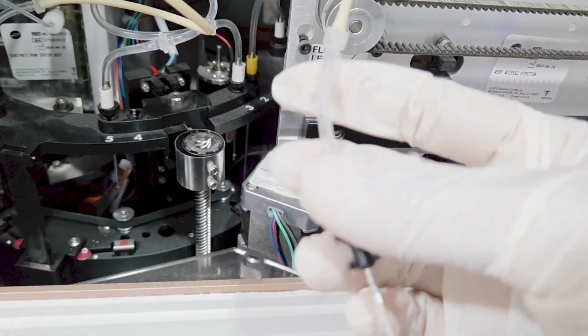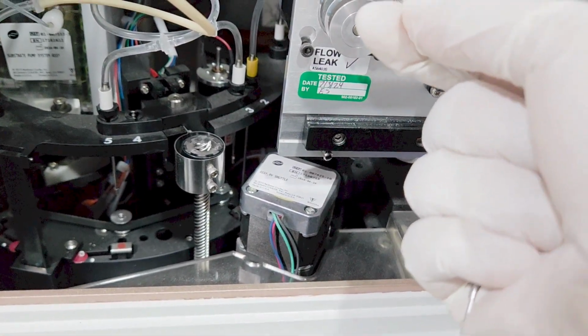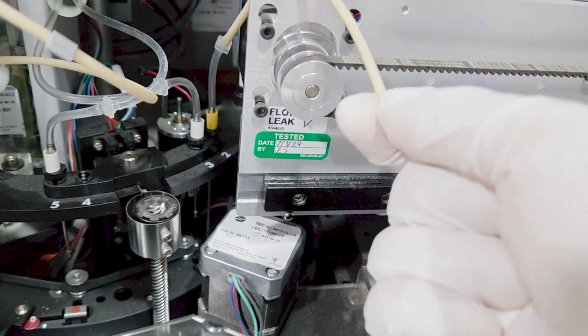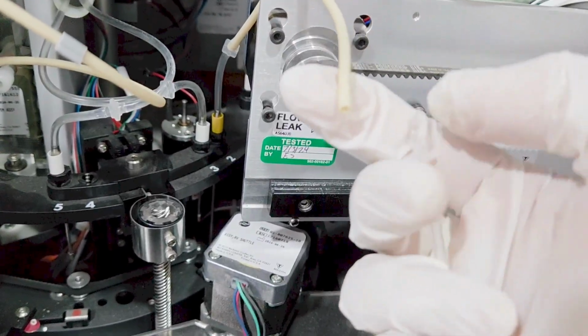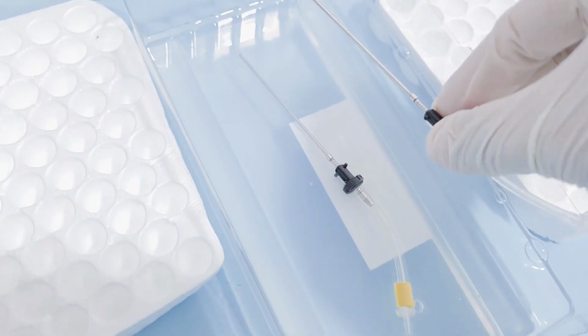Once the probe is detached from its holder, we carefully disconnect it from the main tubing system. The same process is repeated for all 3 probes, that is for number 6, number 4, and for number 2. After successfully removing the old aspiration probes, we can now install the new probes.